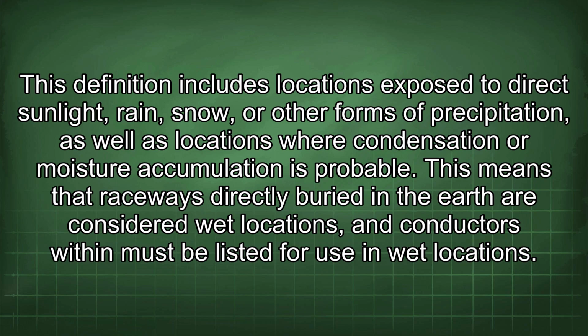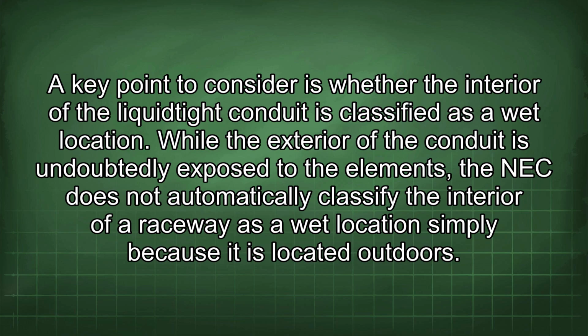This definition includes locations exposed to direct sunlight, rain, snow, or other forms of precipitation, as well as locations where condensation or moisture accumulation is probable. This means that raceways directly buried in the earth are considered wet locations, and conductors within must be listed for use in wet locations. A key point to consider is whether the interior of the Liquidtight conduit is classified as a wet location. While the exterior of the conduit is undoubtedly exposed to the elements, the NEC does not automatically classify the interior of a raceway as a wet location simply because it is located outdoors.